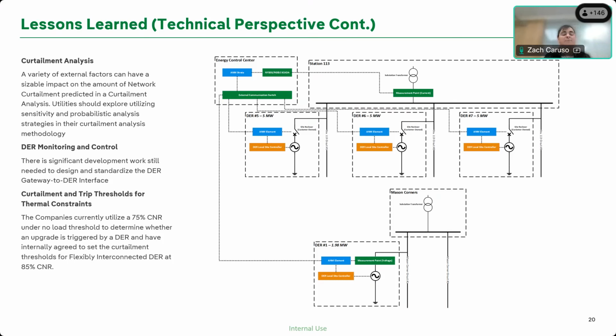And we've also talked about, or I mentioned briefly, the 75% rating for thermal capacity. When you start working with flexible interconnections, you can move those operating limits closer to an operational limit, right? To how much loading am I comfortable operating this transformer up to, and less of a planning approach, where I need to leave space for small DG. And so we use 75% for our static ratings, but we're able to go to 85% of the rating for flexible. And so that gives us a 10% capacity bonus just by moving to flexible, right? That capacity is free, and there's no curtailment associated with it.